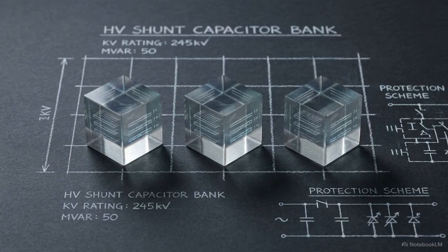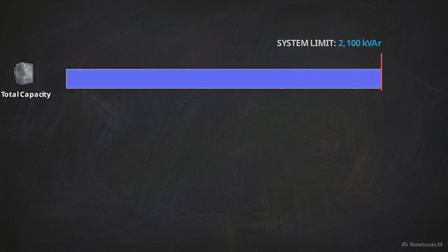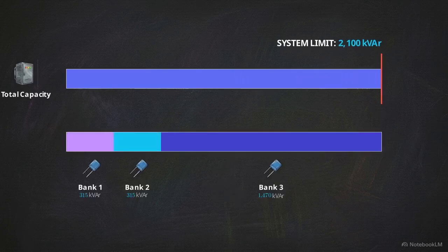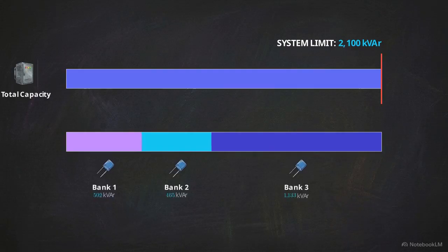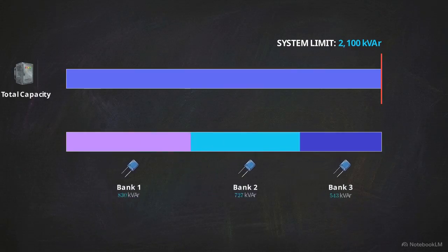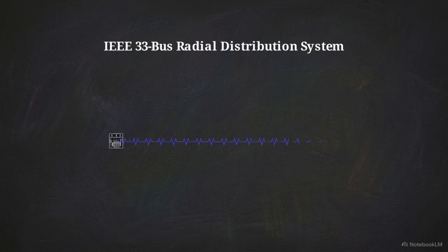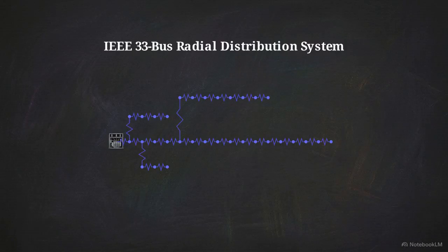To map a solution, we will look at a precise objective: optimizing the placement of exactly 3 fixed shunt capacitor banks within a radial network. The system will operate under a strict constraint. The total reactive compensation across all 3 banks is firmly capped at 2100 kVAR. Our testing environment is the IEEE 33-bus system. It's an industry-standard radial distribution network known for its long, high-impedance branches, which makes it highly sensitive to reactive flow imbalances.